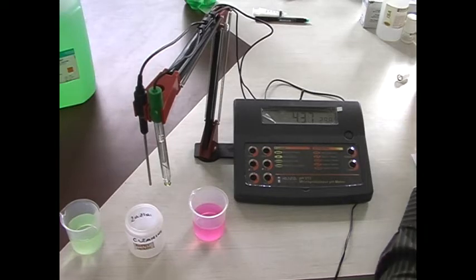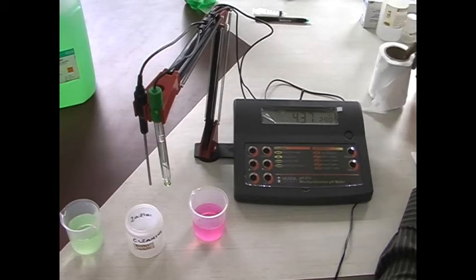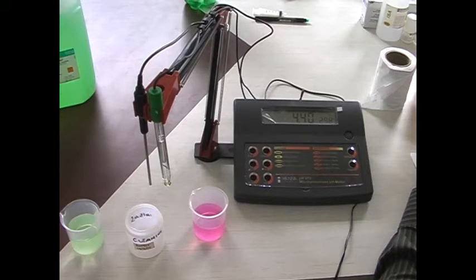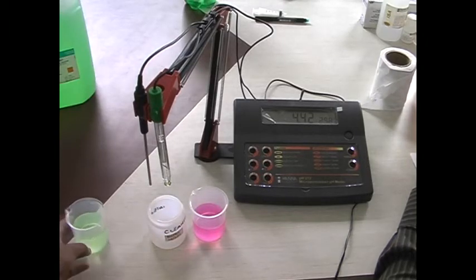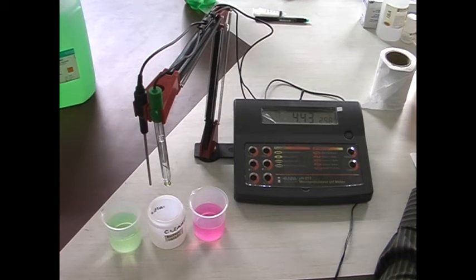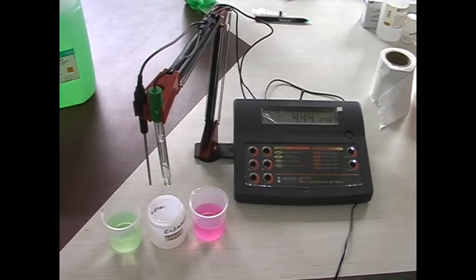Basically, HANNA recommends to calibrate the instrument often, especially if high accuracy is required. The instrument should be recalibrated whenever the pH electrode is replaced, at least once a week, after testing aggressive chemicals, after pressing reset, or if higher accuracy is required. But normally for better accuracy you can calibrate your meter on a daily basis. So first we will see the calibration process.